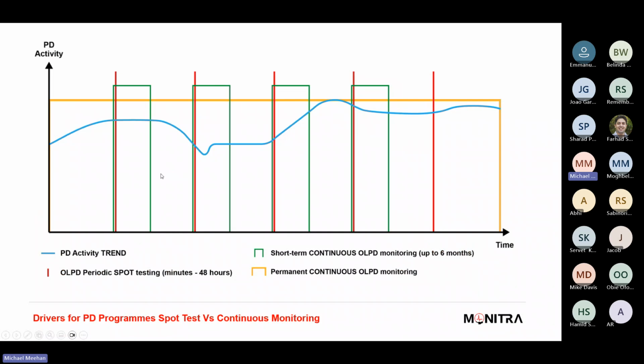frequent maintenance regime. So if we look at the red lines here, that would be a spot check, we would call it. So that could be every year, could be whatever frequency you can think of. But when you look at the difference in PD here to here, you might start to think, why is there less PD here? And then you test here, and then you've sort of confirmed, all right, this one was an anomaly. And then all of a sudden you test again, and now it's up here. So the point I'm making there is really PD does move around. You do need to look at those phase resolved patterns. There is other things you need to look at other than just PD magnitudes. And there is a science behind it.